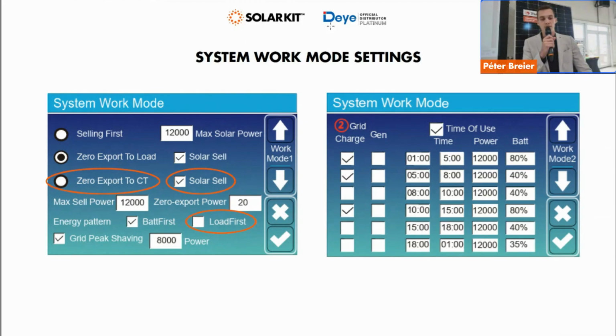And also, you have energy pattern here, which you should usually set to load first, because load first will try to give energy to the loads instead of charging the battery. And you should use bat first if you have unstable grid connection and you always want to keep the batteries charged up. On the system work mode second page, there is a very important mark to make.